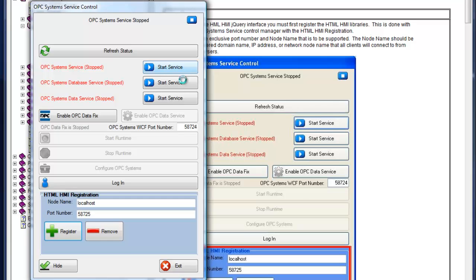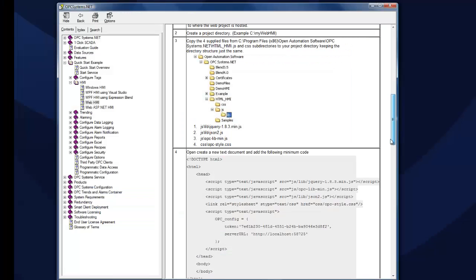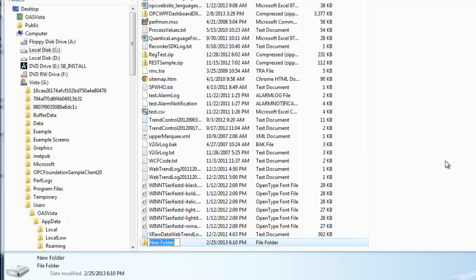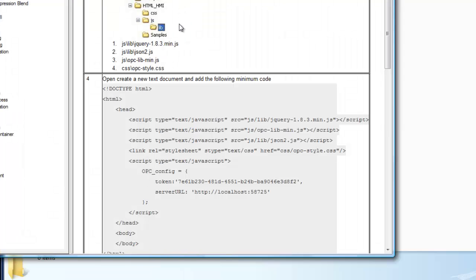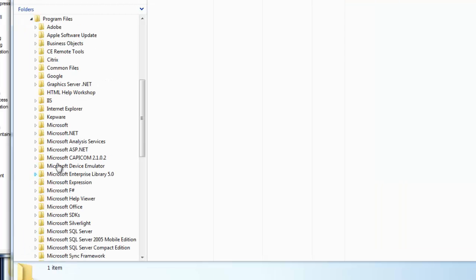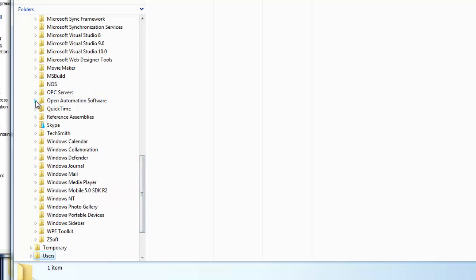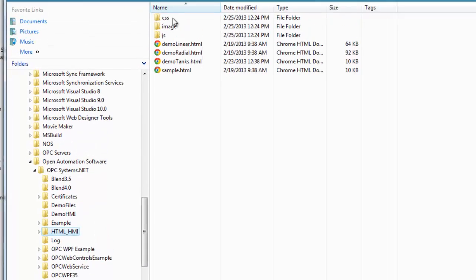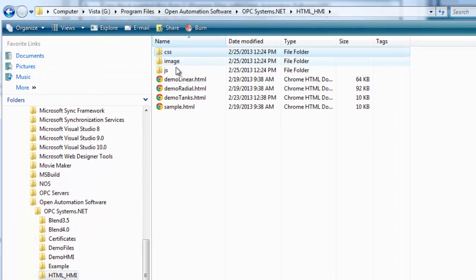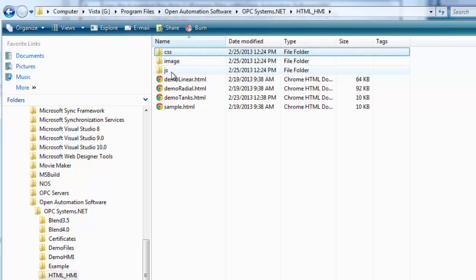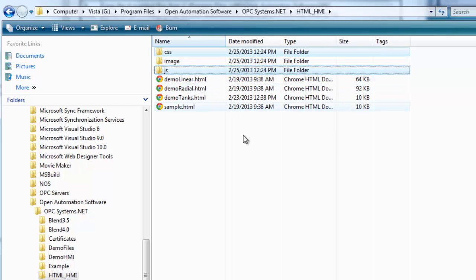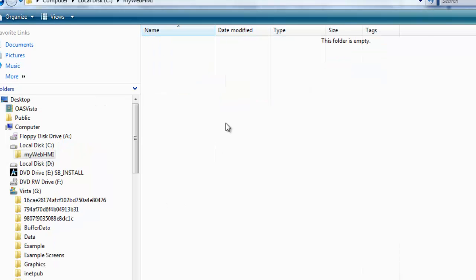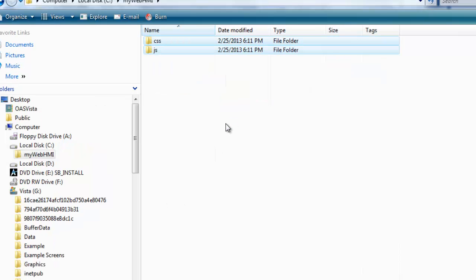Now we'll start the services. We'll continue on to the next step in the help guide, which is to create a directory on the local hard disk. We'll create a directory on the C drive called mywebhmi. We'll then copy some files from the installation directory of opcsystems.net into this directory. This is typically under program files or program files x86, open automation software, opcsystems.net, and then html_hmi. There we want to copy all the files out of CSS and JS subdirectories, and we'll copy those directories intact. We'll copy them right into the mywebhmi directory.